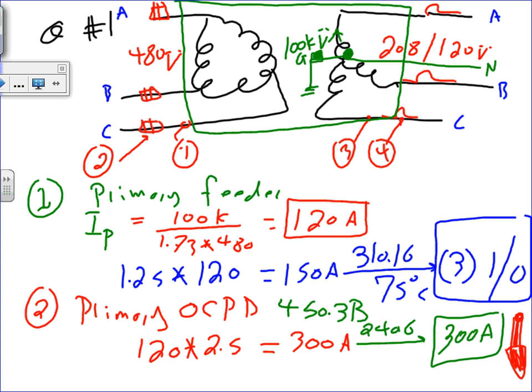And I'm going to use a cable here that says, where are we? Number 5. And I want to go grab that bonding jumper, number 5, number 6. I want to size these two for the transformer. I create a separately derived system. That's what we call a separately derived system, right at the transformer. There's a bar that's for ground and a bar for the neutral. You tie the two together, and from the bar for the ground, you go to Mother Earth, or you can go to the steel of the building. We'll get into 5 and 6. Let's do 1 and 3 and 4. Any question about 1 and 2, Mr. Rabab? Yes, sir. Can you explain to me why that's a separately derived system?